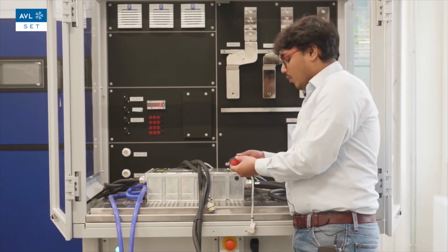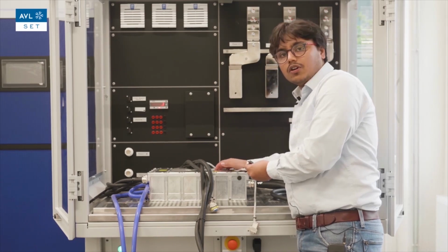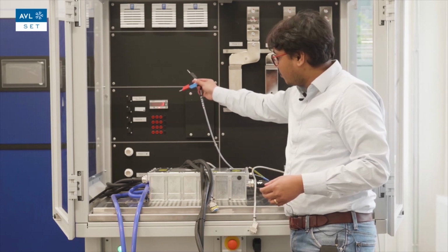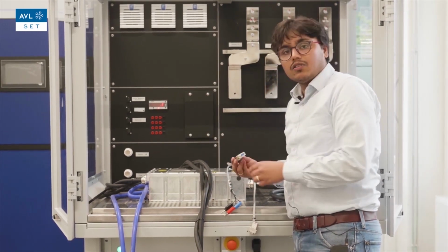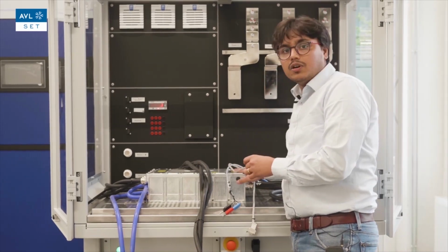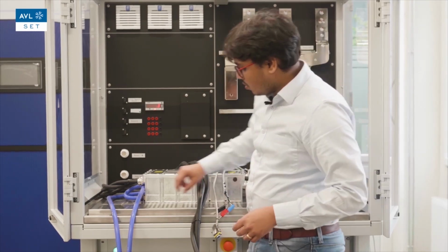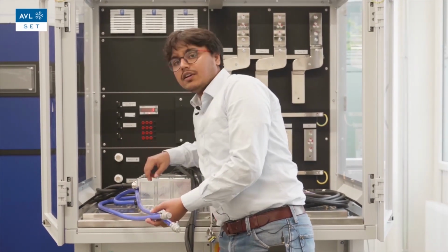We have one more low voltage power supply connector here. In order to supply this inverter with low voltage power, we have this connector and we will make a connection. Then we have a control interface between the inverter and the control PC, and also a water cooling circuit connection for this particular inverter, which needs to be connected with the cooling unit, for which we have the terminal inside this particular inverter.